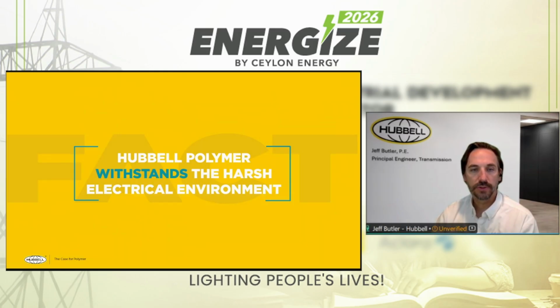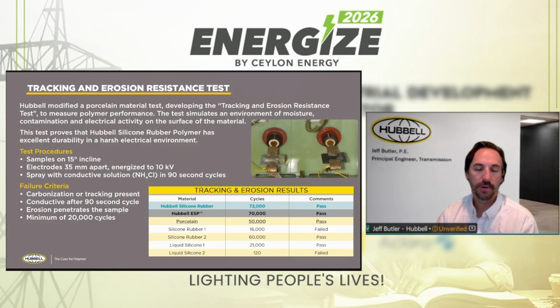And then another test was adapted from a porcelain test, and this is very similar to the inclined plane test that is used today. I don't know if anyone might be familiar with the standard IEC 60587, but this was an inclined plane test developed from the porcelain standard. As I mentioned at the beginning in the history of Ohio Brass, originally we were manufacturing porcelain insulators, so this was a test that we used to evaluate the integrity of the porcelain samples, and we adapted it for evaluating the integrity of polymer insulators. In that regard, for porcelain we had a minimum threshold of 50,000 cycles.